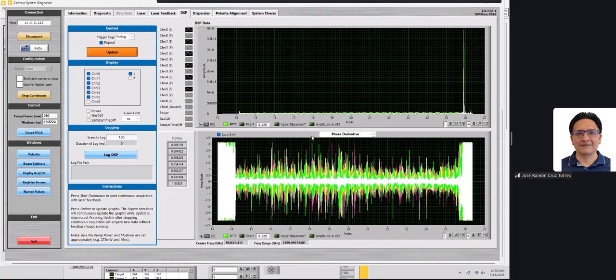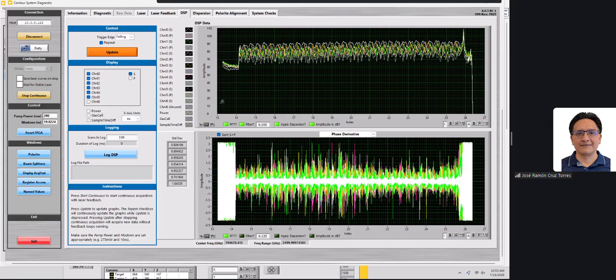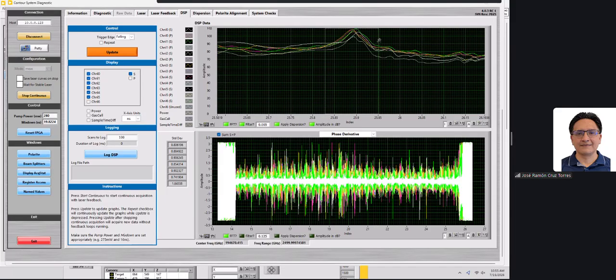here and toggle all these guys, bring down the filter a little bit, and then basically what we're trying to do is read the exact time delay value for this very specific peak. So this is the peak where it's the connector interface. So this guy here.